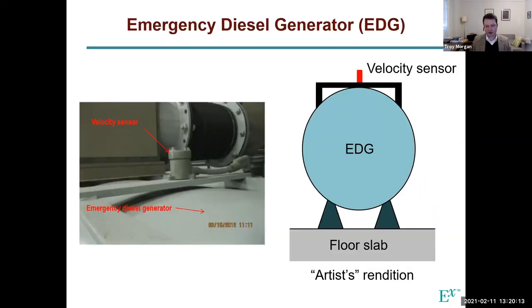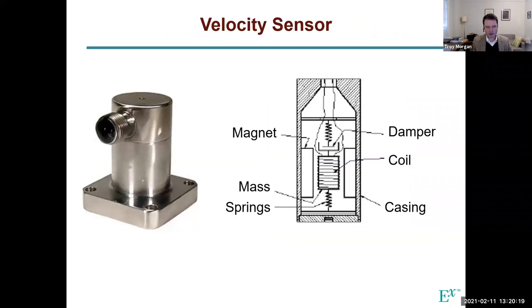And then you've got the generator sitting on top, and then you've got the velocity sensor up here, where the motion is measured. And if you look at this sensor, it actually has some nice properties. It's basically a mass, which is the coil, a steel element wrapped in a coil that then passes through a magnet. And just through Faraday's law from basic physics, if you move a coil through a magnet, you'll generate a voltage as a result based on the velocity.